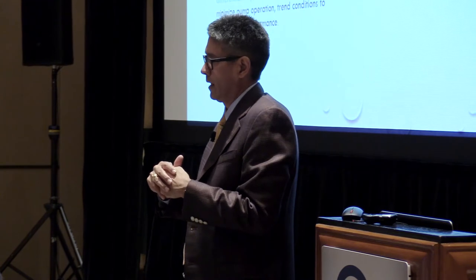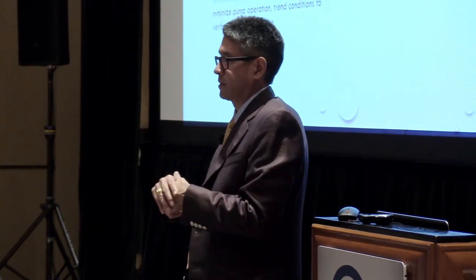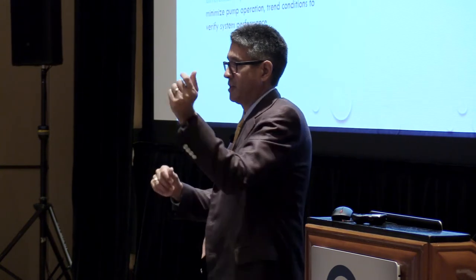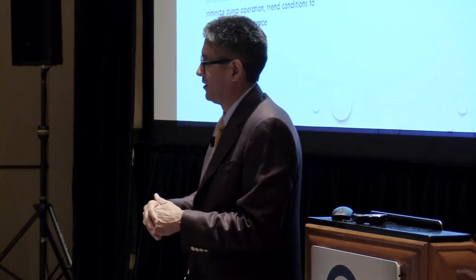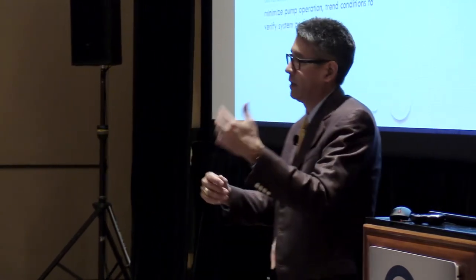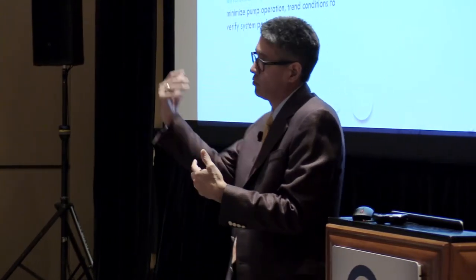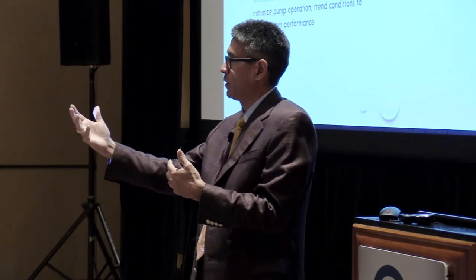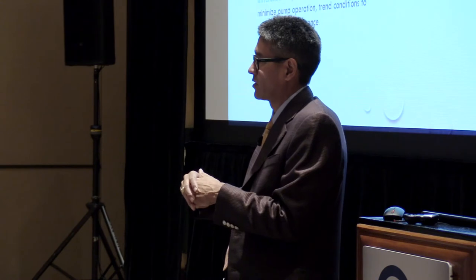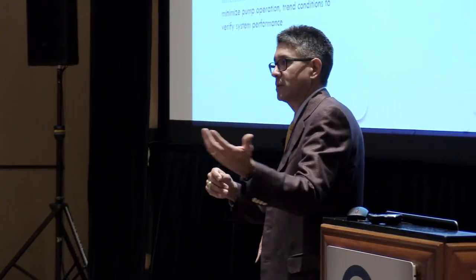And the one guy, I laugh, he kept dropping his. He goes, so what are you trending? He says, I forgot to set that up, but I don't get any complaints. So I just keep going until I get no complaints. It was interesting because then once he got to that point, we went back and checked what we used and what we thought set that DP set point. Turned out we were probably at 85% of flow, but it was still enough flow to maintain that space condition.